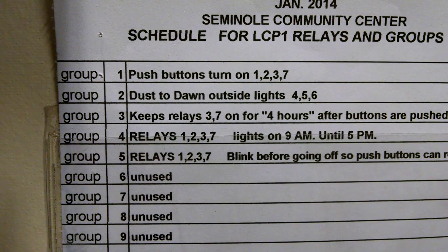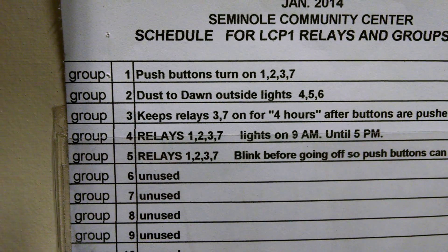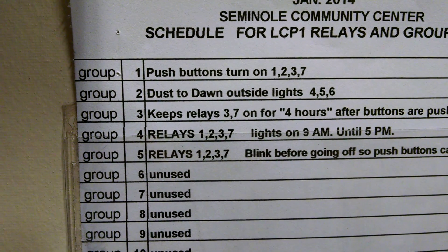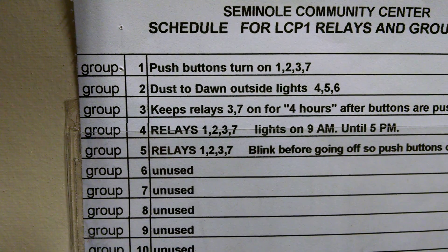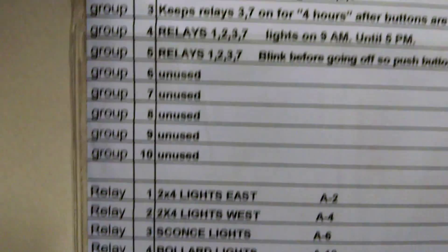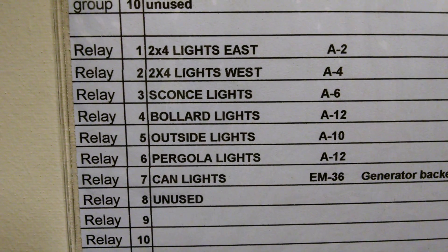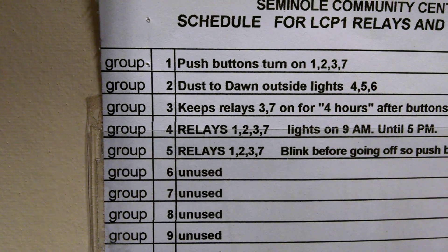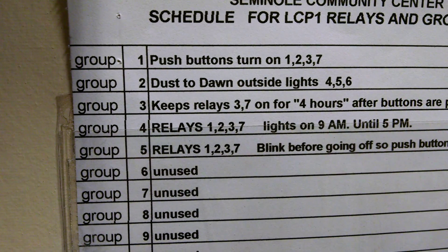Group number one says that the push buttons are going to turn on relays one, two, three, and seven. The dusk-to-dawn lights outside are on group two — dusk-to-dawn relays are four, five, and six: bollards, outside lights, and the pergola. What they're going to do is turn on a half hour before sunset and shut off a half hour after sunrise.